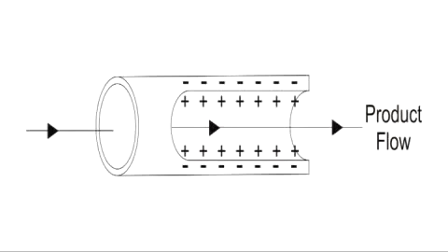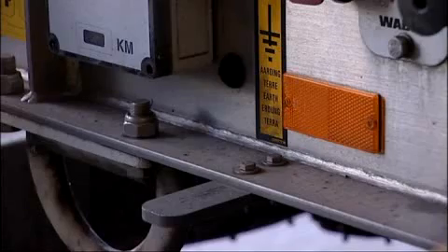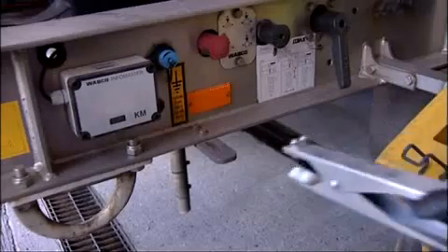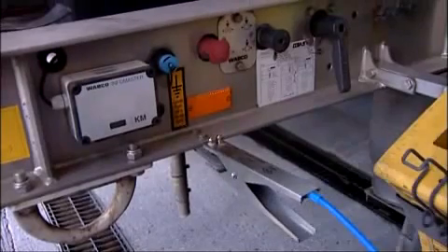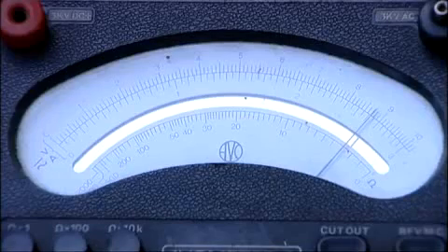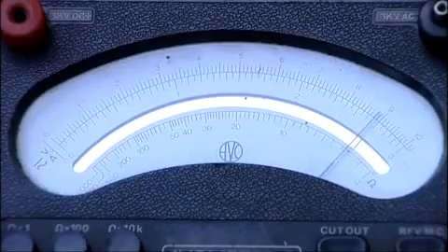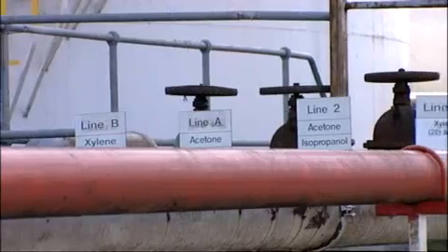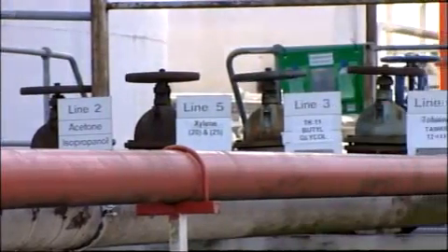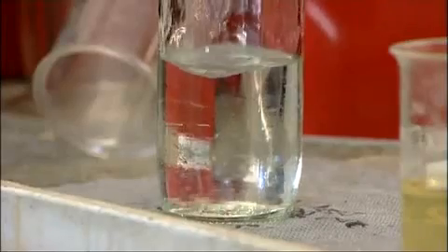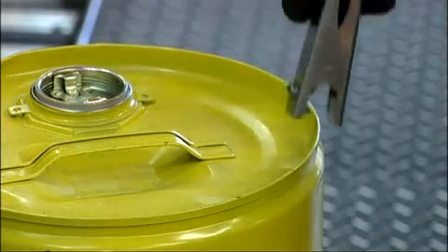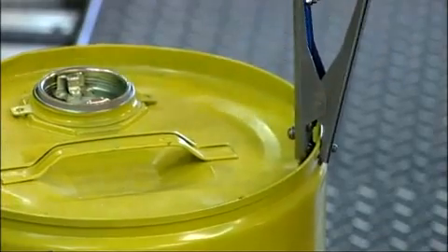Negatively charged electrons move across the boundary between the two bodies and are then unable to return. The charge on the containment system can be dissipated quickly by earthing, but the charge in the liquid remains and is slowly dissipated, depending on the conductivity of the liquid. How quickly the static electricity charge builds up depends on a number of factors: turbulence of the liquid, the speed and contact of the liquid with the surface area of its surrounding equipment, the presence of impurities, and how quickly the earthing equipment can remove the charge.